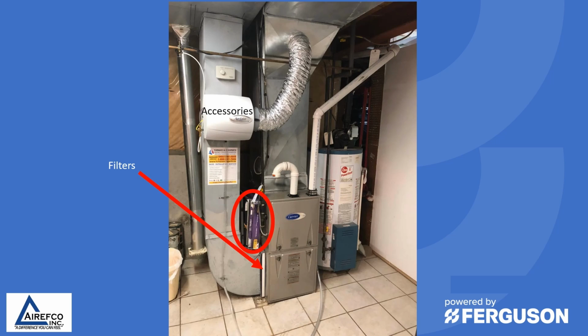So airflow is critical to the proper operation of a gas furnace, so we want to make sure right off the bat that the filters are clean and we have good airflow. The next thing we want to look at is the venting. This vent pipe goes up one elbow and then it elbows back and out through a sidewall. So you want to make sure that the furnace is vented according to the manufacturer's specifications.